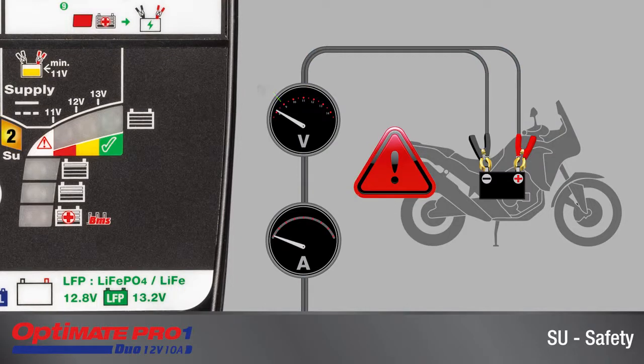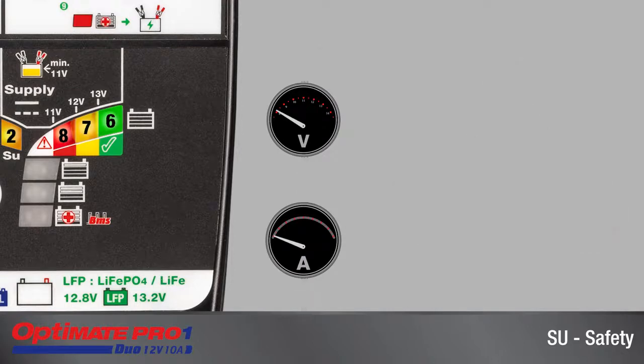If the SU LED blinks while LEDs 6, 7, and 8 are off, a fault condition has been detected. This might be a reverse-connected battery, a short circuit or overload, or AC power was interrupted during SU mode. Correct the fault condition, then push and release the push button. Output is restored when LED 2 turns full on together with LEDs 6, 7, and 8.